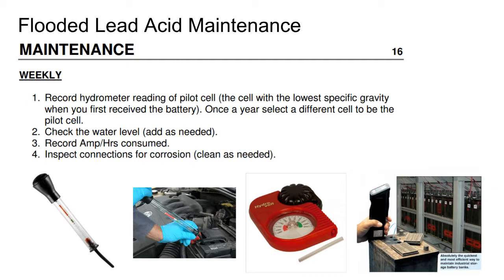But the takeaway is you have to do that maintenance in order to maintain your battery warranty. They say it's a weekly task. It's more of a task that ebbs and flows based off your battery usage. And so in the springtime and in the fall, this task may be once every 3 weeks, whereas in the summertime and the winter, every week is what you can expect.